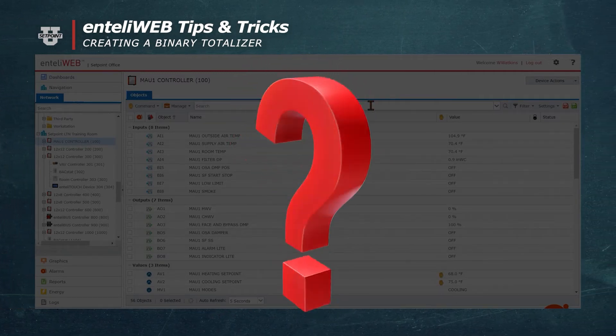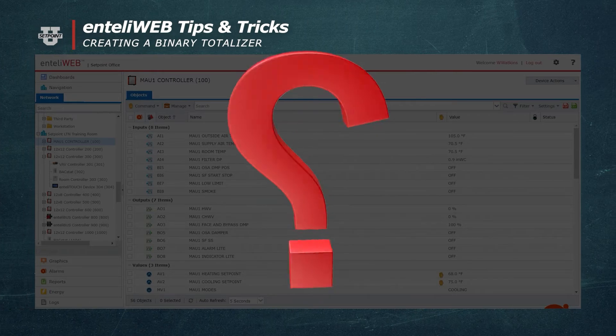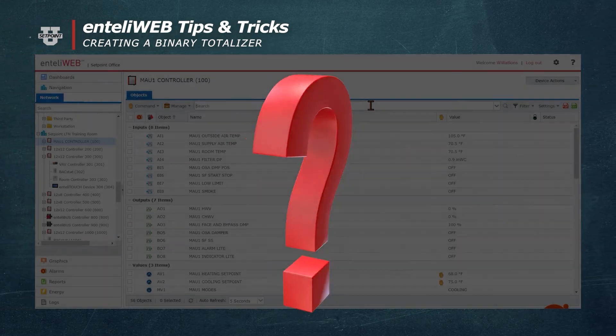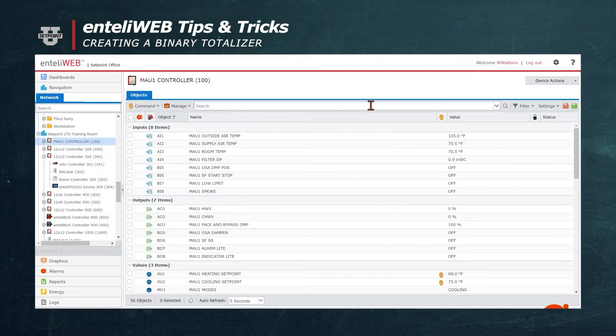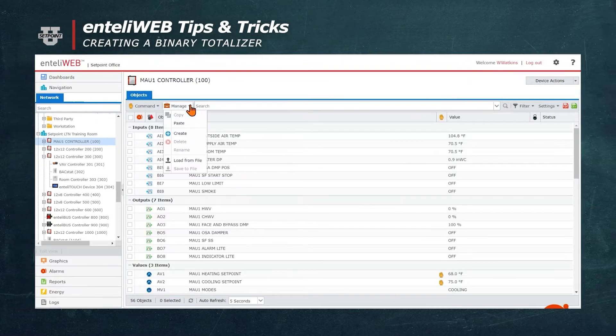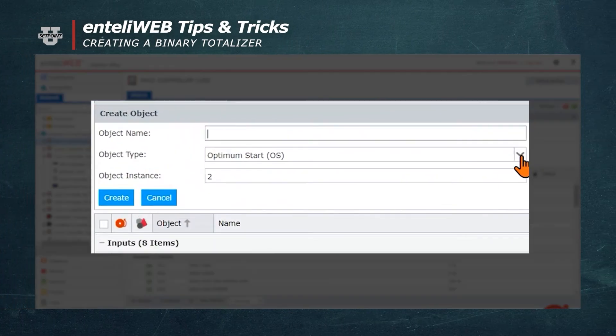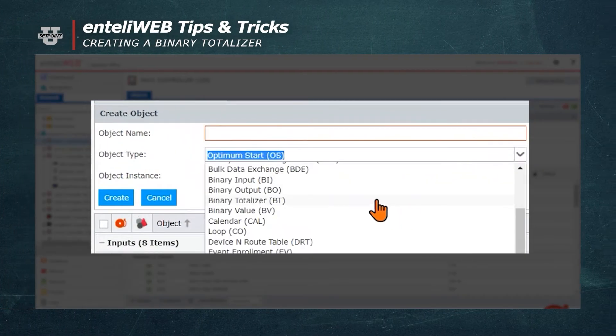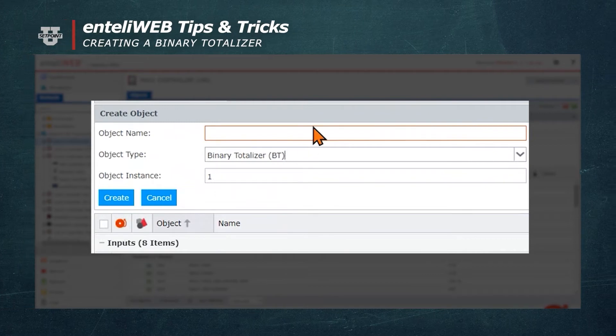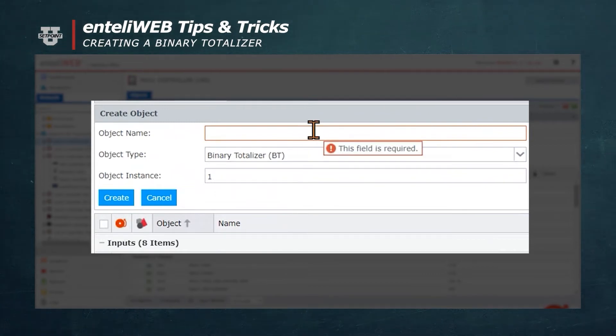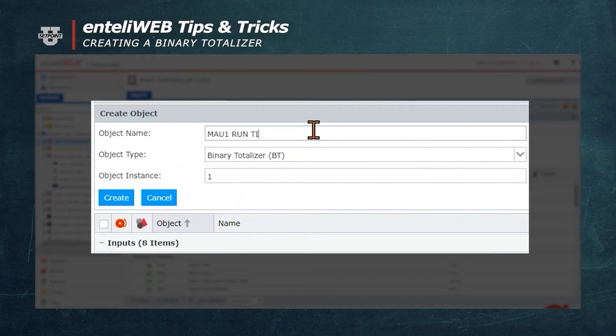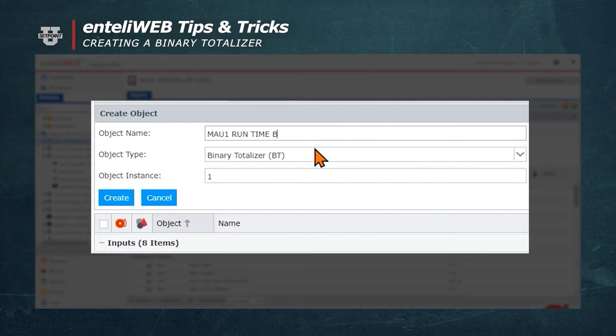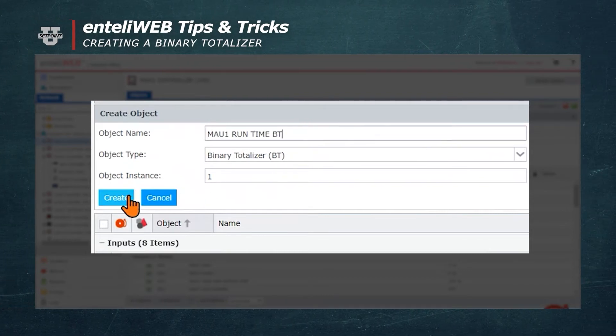By monitoring the status, any time the equipment operates, the time will be documented. We'll start by going to Manage and clicking Create. We're going to scroll down and select BT for Binary Totalizer. We'll call it MAU1 Runtime. Now we're going to hit the Create button.